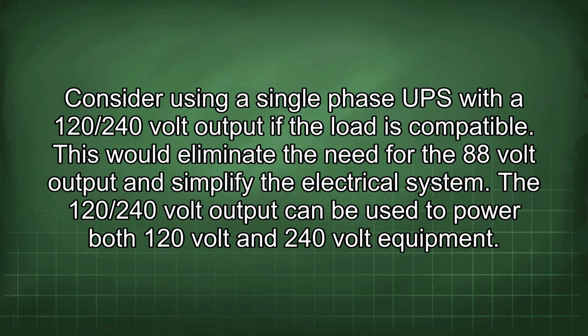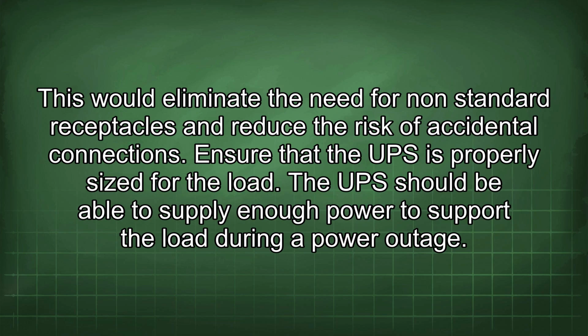Consider using a single-phase UPS with a 120/240 volt output if the load is compatible. This would eliminate the need for the 88-volt output and simplify the electrical system. The 120/240 volt output can be used to power both 120 volt and 240 volt equipment. This would eliminate the need for non-standard receptacles and reduce the risk of accidental connections.